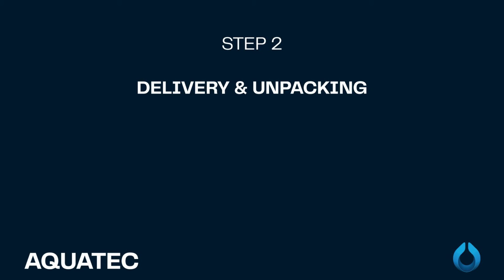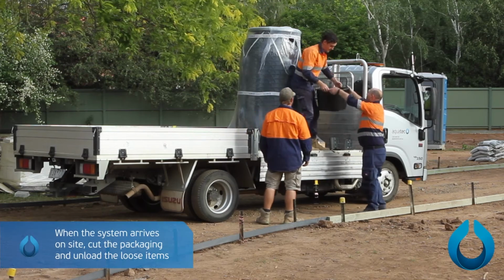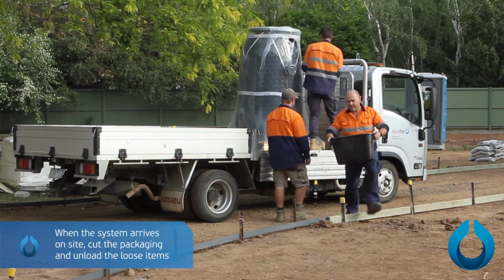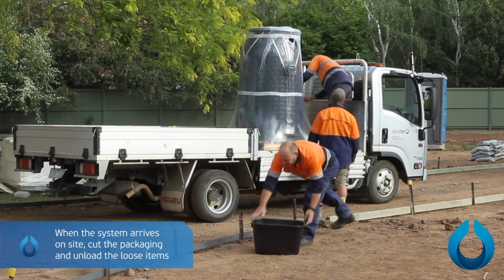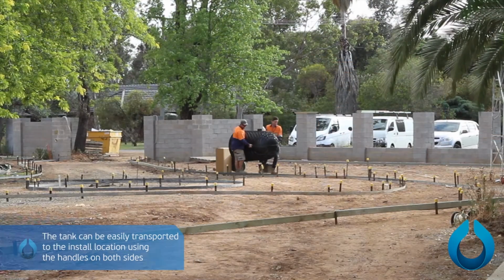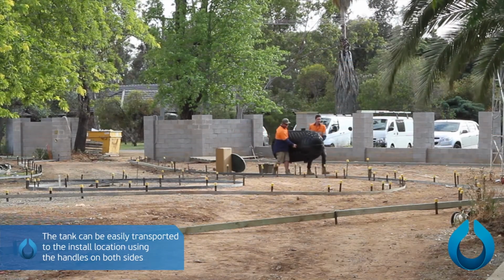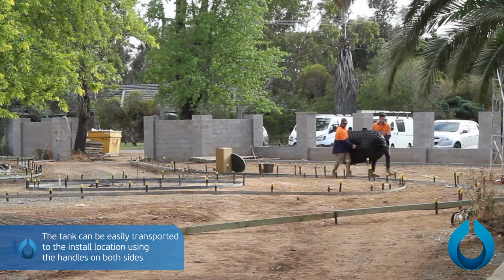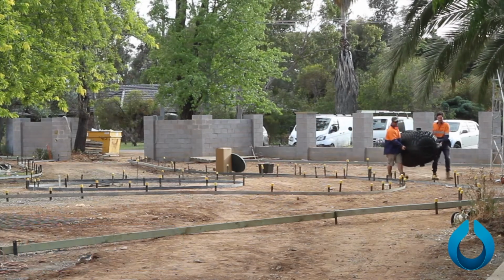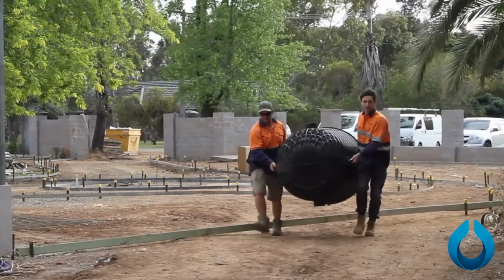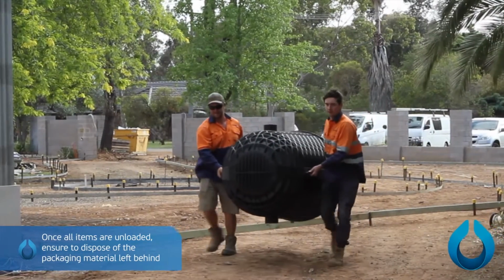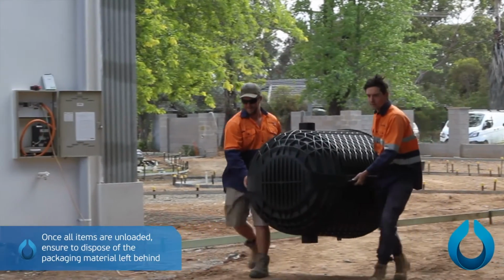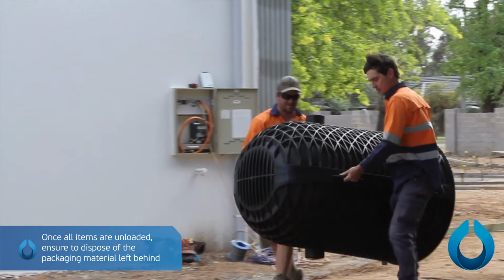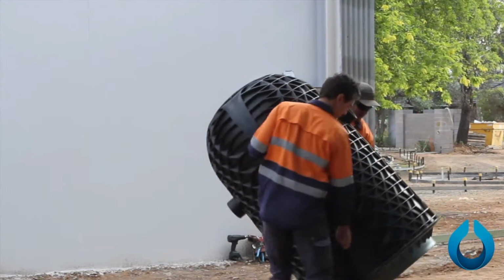Step 2. Unpacking the pressure sewer system. When the system arrives on site, cut the packaging and unload the loose items. Any lifting from personnel should take into consideration health and safety requirements. The tank can be easily transported to the install location using the handles on both sides. Once all items are unloaded, ensure to dispose of all the packaging material left behind.